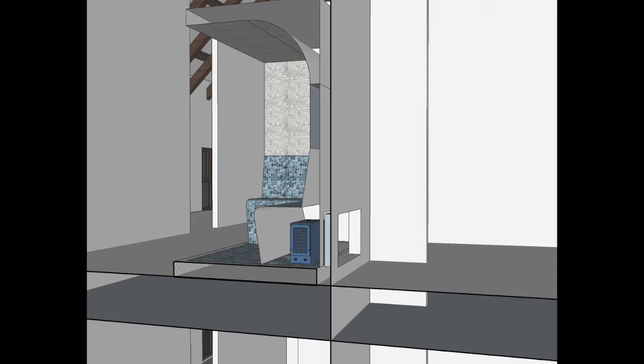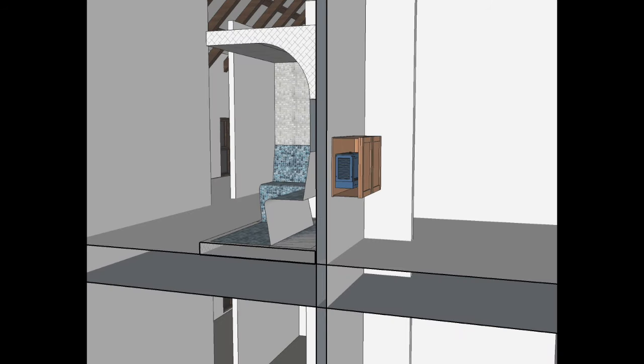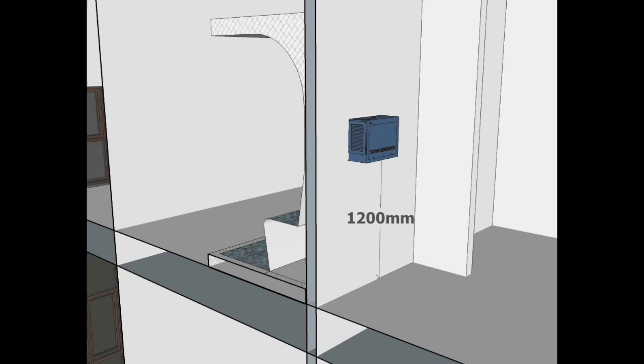Access must be from outside of the steam room if installing under benches, or in an enclosed cupboard adjacent to the room. The ideal location needs to be easily accessible and at between waist and chest height, approximately 1,200 millimetres from the floor to the base of the unit.